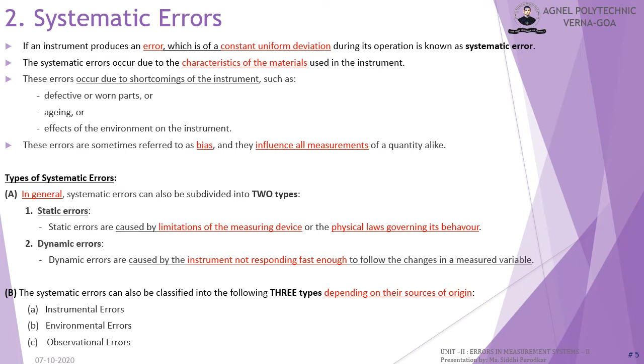Instrumental errors depend on the type of the instrument used. For example, in D'Arsonval movement or in PMMC instrument, instrumental errors can occur due to friction in the bearings of various moving parts, due to irregular spring tensions or stretching of the spring, or reduction in tension due to improper handling of the instruments, or finally due to overloading of the instrument. Other causes of the instrumental errors are calibration errors and failure to set the instrument to zero, which causes the instrument to read either higher or lower reading than the actual reading along its entire scale.